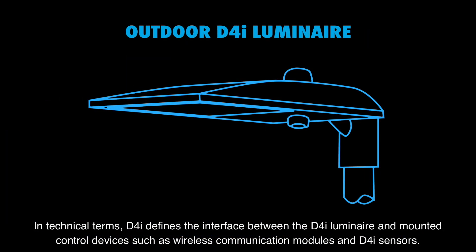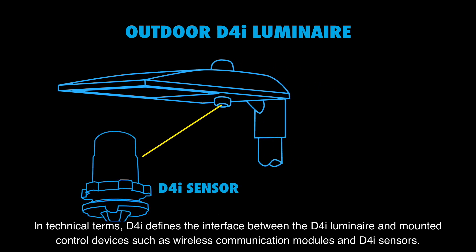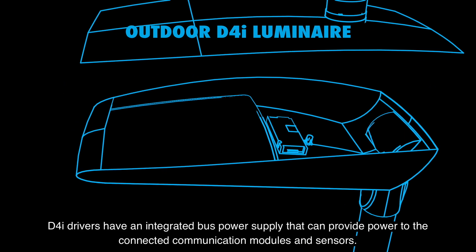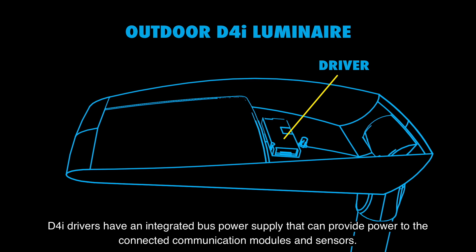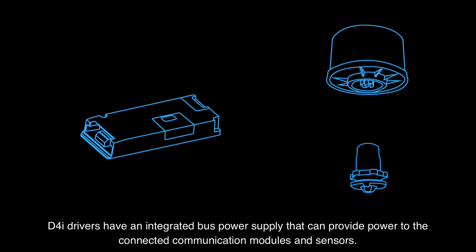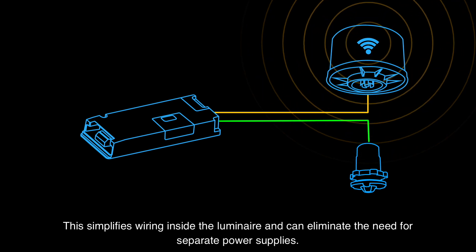In technical terms, D4i defines the interface between the D4i luminaire and mounted control devices such as wireless communication modules and D4i sensors. D4i drivers have an integrated bus power supply that can provide power to the connected communication modules and sensors. This simplifies wiring inside the luminaire and can eliminate the need for separate power supplies.